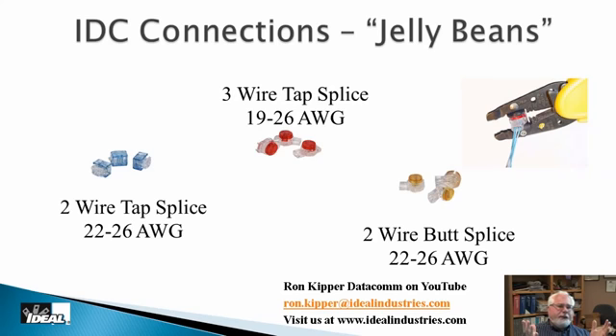It taps a line like the red one. But you know how we had to cut the wire to use the red one? The blue ones have a slot running all the way down to one side of them. And I'm going to take this conductor, I'm going to tap, and I'm going to put it inside that slot. And there's a hole on the end of that little blue one that I can lay a tap wire out of. And the big difference is that when I crunch that blue one down with a plier, it does not cut the wire you're tapping.